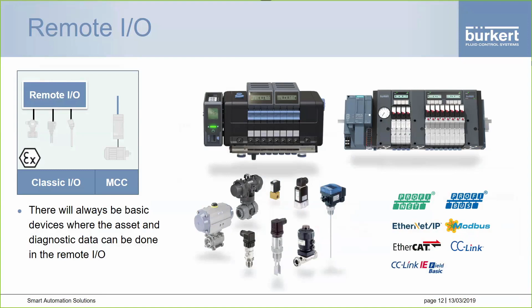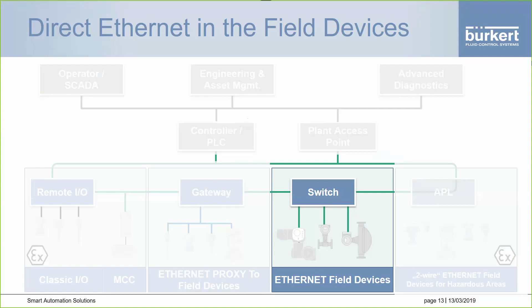This diagnostic info doesn't go all the way down to the final element in the field, but at least to the I/O level. The second way to take Ethernet to the field is directly, using devices that have Ethernet mounted on them. These are normally higher level devices, like specialty flow meters, modulating valves, positioners, and electric control valves, where the price point and complexity make direct Ethernet connection sensible.